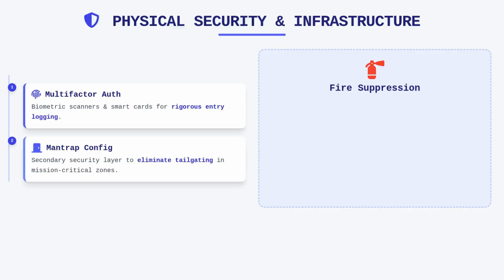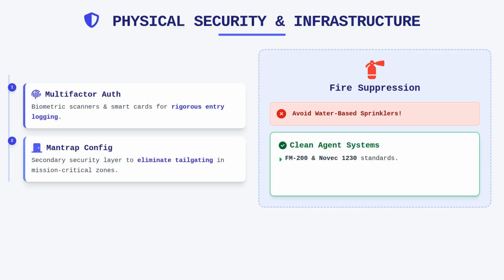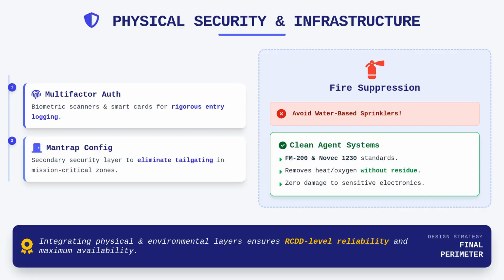Fire suppression strategies must prioritize equipment safety over traditional water-based sprinklers, which would be disastrous for electrical hardware. Clean agent systems, commonly FM200 or Novec 1230, are the industry standard because they extinguish fires by removing heat or oxygen without leaving residue or causing damage to sensitive electronic components. By integrating these physical, environmental, and security layers, you create a facility that is robust enough to handle the demands of a high-density network backbone. Each detail contributes to the overall availability and reliability required for RCDD level certification.